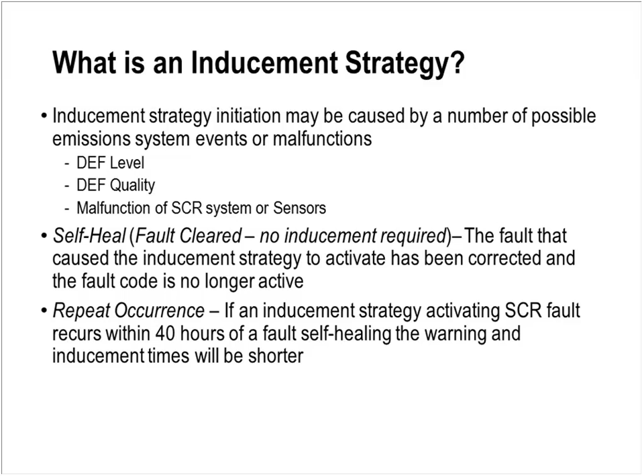So already mobile emergency engines have an override facility to prevent inducement shutdown from occurring. Things such as fire trucks and ambulances and off-highway firefighting equipment such as bulldozers and track-type units already have an override system. And EPA are now working on a similar provision for stationary engines. So we anticipate that within the next 6 months there will be a provision for us to provide an override strategy. So if there is a genuine emergency and the units are running, if we have a fault on our SCR system, then the fault can be overridden and the unit continue to operate until the emergency period is over.